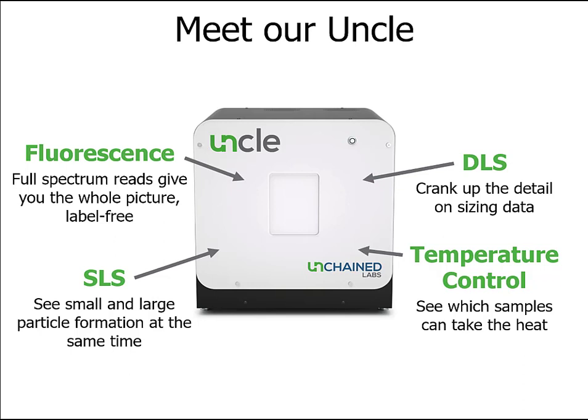UNCLE can see the full spectrum for fluorescence, giving you the option to look at protein intrinsic fluorescence and evaluate tyrosine and tryptophan fluorescence, or use any of an arsenal of fluorescent dyes. Simultaneous with that fluorescence experiment, you can use static light scattering to monitor how the same sample aggregates. UNCLE uses SLS at two wavelengths so you can track small and large particles at the same time. Dynamic light scattering is UNCLE's third detection method—a highly sensitive technique to give you details about your protein's size and size distribution. DLS is also powerful for understanding what's in your sample, and can be used to quality check proteins before or after an experiment, or to get orthogonal confirmation of SLS aggregation data.